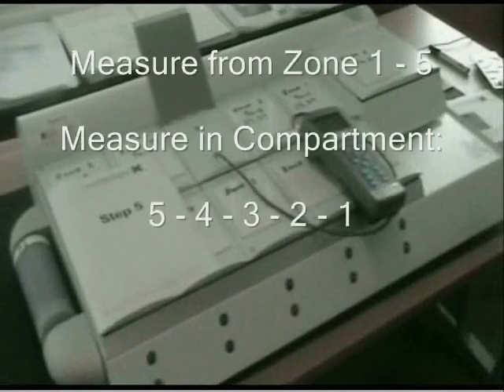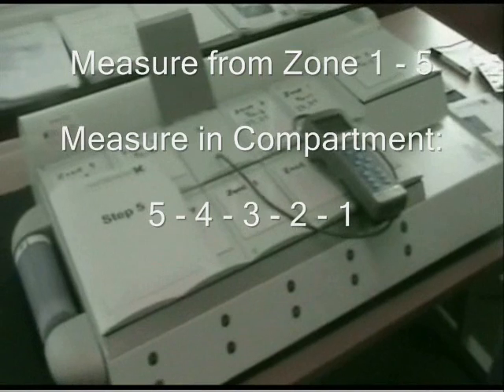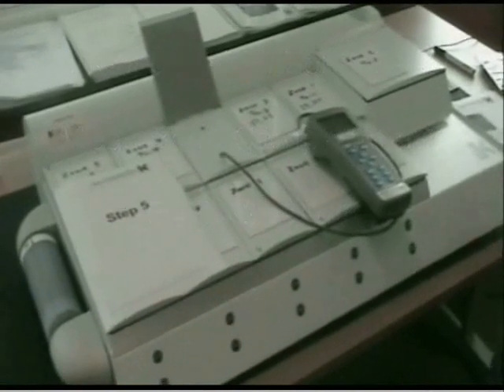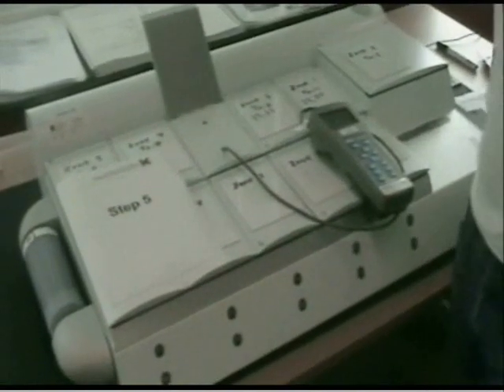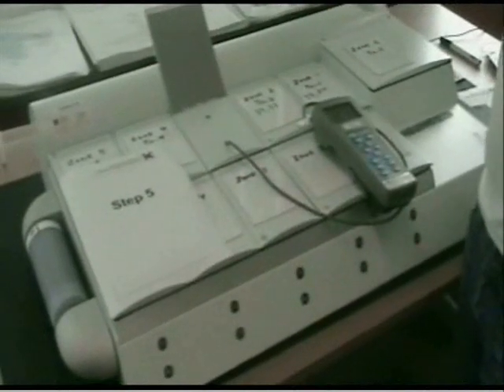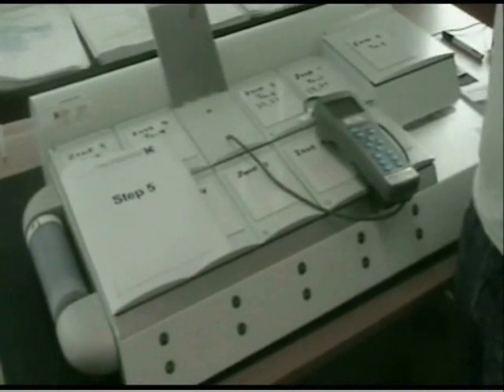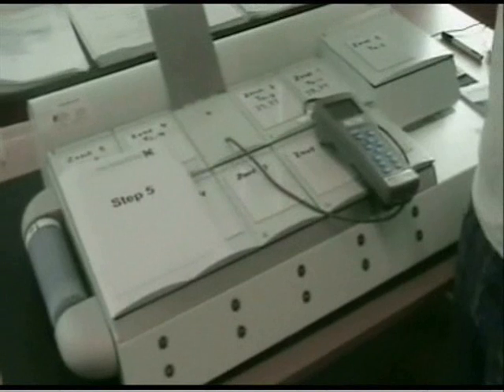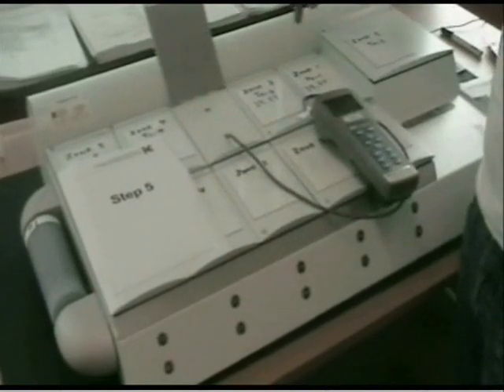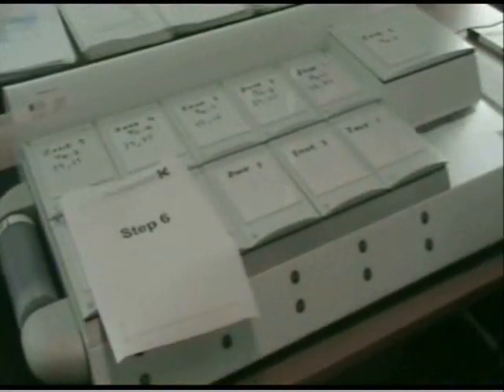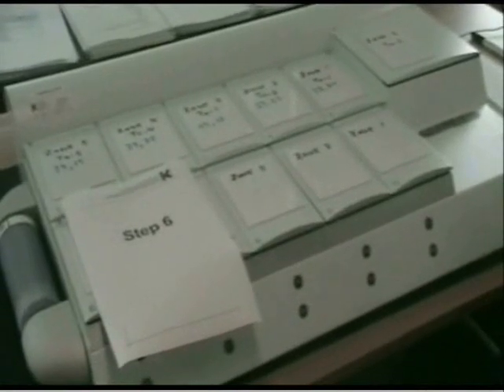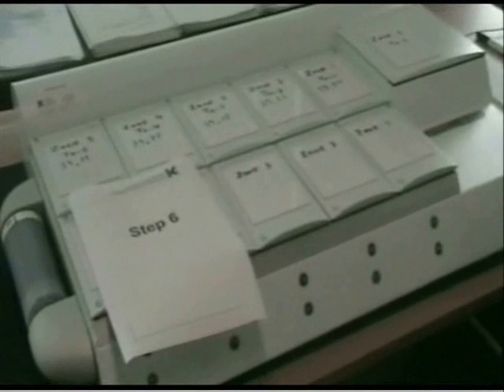Well, I finished the measurement on zone 2, that's 39.23, and I've written it down on the magnetic pad, and we've moved on to zone 3. I'll be measuring in zone 4 and zone 5 afterwards, and I'll just repeat the process like we've been doing on zone 1 and zone 2 so far. We have all the values for the 5 zones completed, and in the next step we will adjust the calibration values on the G185 accordingly.